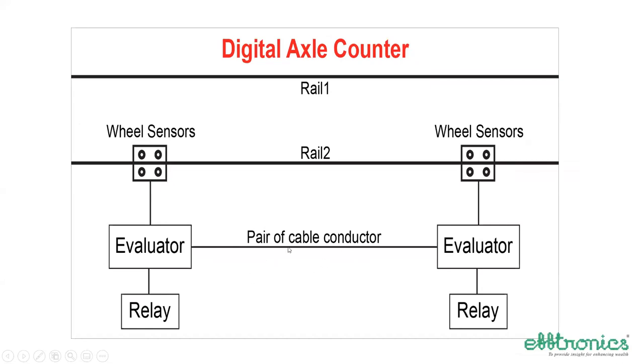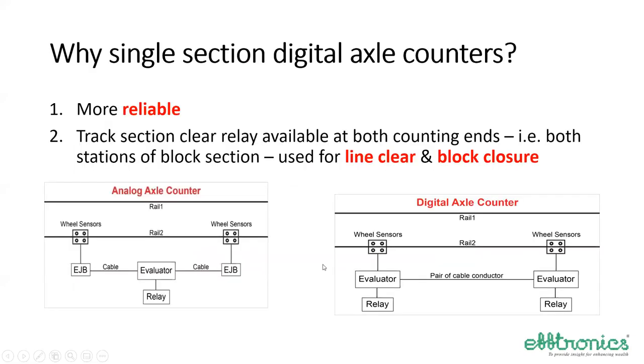What happens in case of a cable fault here? Will both the relays pick up? No, they are not supposed to, because in the absence of communication between the evaluators, the fail safety of the system is affected. That means the wheel counts cannot be transferred from one to the other. That is why the relay drops. But there is a time delay, about 200 milliseconds or so. This is it actually. So analog axle counter, digital axle counter, you can make out.